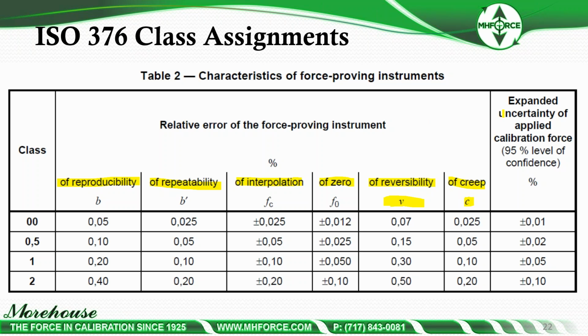And then ISO does a very nice job in the standard with the expanded uncertainty of the applied calibration force. So if I have an applied calibration force with an expanded uncertainty of greater than 0.01, I cannot assign a class 00 loading range. If I have one greater than 0.02, I cannot assign a class 0.5. So if you look at people's scopes of accreditation and they're saying, hey, I'm 0.04, then guess what? The best they can do is class 0.5, because 0.04 is between 0.02 and 0.05. If they're saying they're at 0.05, there's a good chance that the best they can do is only class 1. So it depends on what you need. Typically, if you're calibrating other load cells and you want to continue calibrating in accordance with ISO 376, you're going to need class 00 ranges.